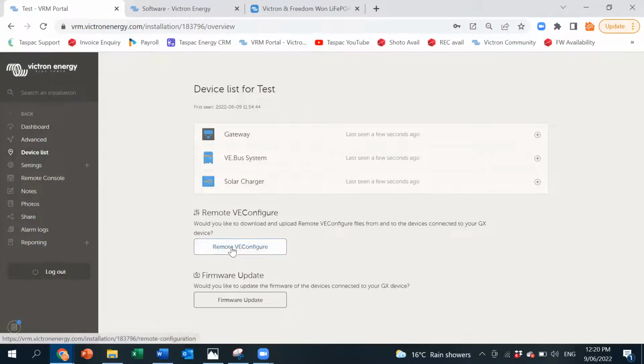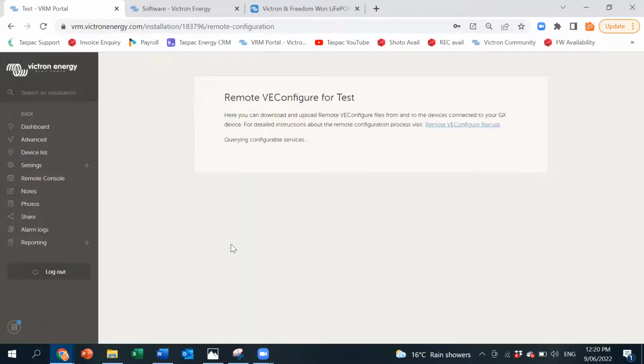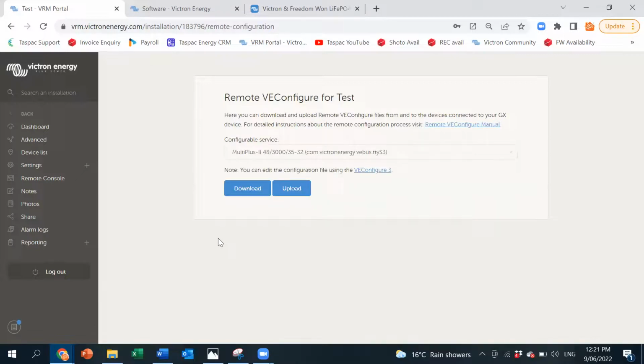Now we go to remote VE configure. This is for configuring the inverter part of the system. We have 3 devices inside the Easysolar: the GX device, which we've already configured, the inverter, which we're about to configure now - you see there it says configurable service - we've got multi plus 2, that's the inverter. So we'll download the software from that. The other thing we need to configure is the charge controller.